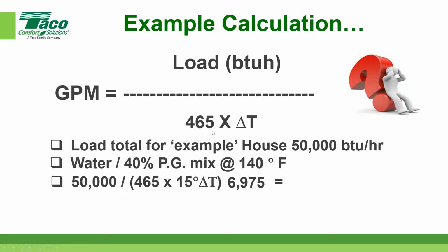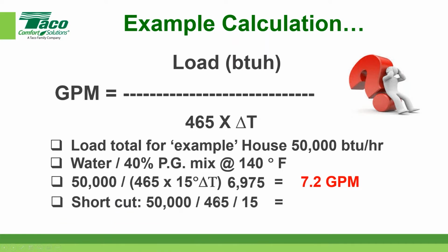So 6975 is what's here. 50,000 BTUs is what's here. If I take 50,000 BTUs divided by 6975, I get 7.2 gallons a minute. Now that's the longhand version. Let me show you a shortcut. You take your load divided by your constant, divided again by your delta T, because the division and the multiplication are reciprocals. This is why it still works: 50,000 divided by 465 divided by 15-degree delta T is still 7.2. Again, I'll give you shortcuts when they're applicable, but I want you to remember the longhand version and why things are like they are.